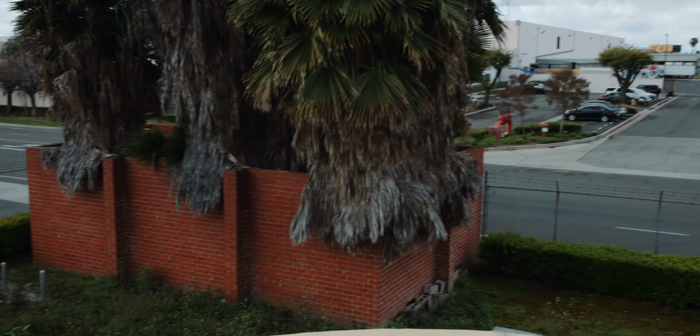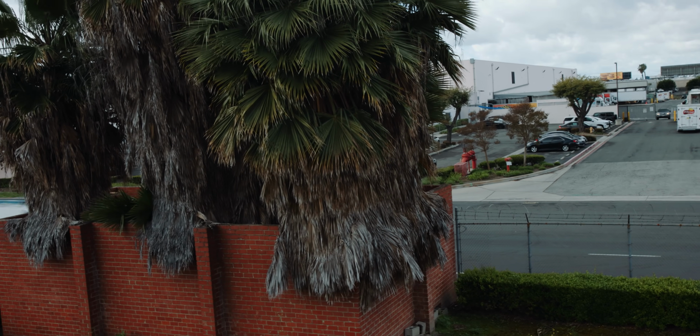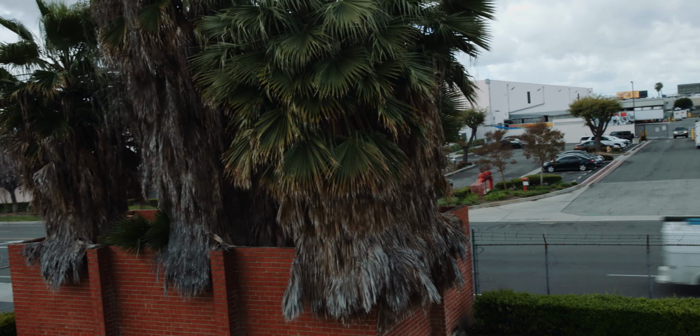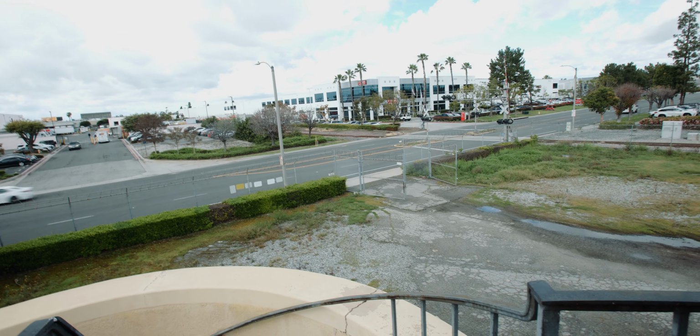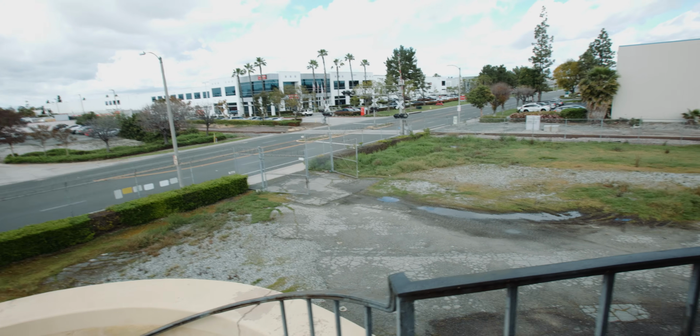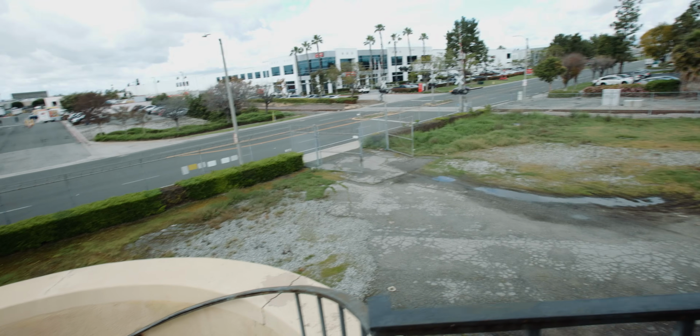That was a big deal because they had to pull a bunch of cables. I remember there was a conduit underground that had these big conductors in it, and they wanted to pull them out, and they could not get them. It's like they were stuck. And they had to literally start slicing the conduit open, like you're cleaning a fish, before they finally got the conductors out. It was really a mess. But they got it, though. So it's just empty brick. It's just empty now, yeah.